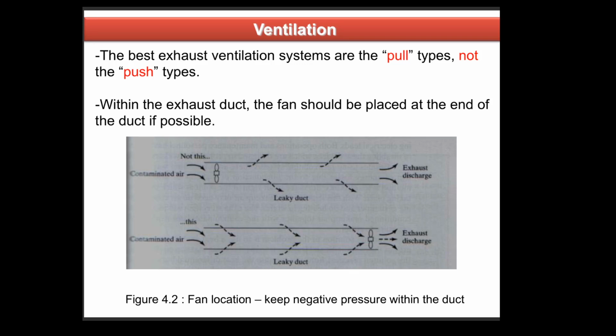Within the exhaust duct, the fan should be placed at the end of the duct if possible. You can see in diagram number 1, the exhaust fan is at the entrance of the duct, and in diagram number 2, the exhaust discharge is there and the exhaust fan is at the outlet of the duct. Contaminated air is entering the system, and at the outlet we have mounted an exhaust discharge fan. The fan location is important. Keep negative pressure within the duct.